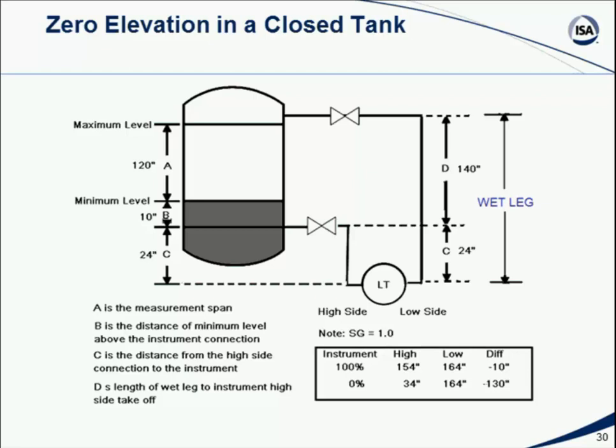And we know that that is a column of fluid that is 140 plus 24 inches in height, because we are 24 inches of elevation below the tap, and we allow the tank level to go up to the maximum level. That's great, but what was a dry leg tap is above the maximum level. So it's actually 140 inches up. So we now have a column of fluid that is 164 inches, and it's there all the time. It doesn't go up or down. In other words, the legs fill up with fluid, and now we have a wet leg that actually is a column of fluid that would be greater than the column of fluid in the tank. The tank's never allowed to go above the maximum level, and that's 20 inches below the tap point where we put the upper tap that was supposed to be a dry leg.